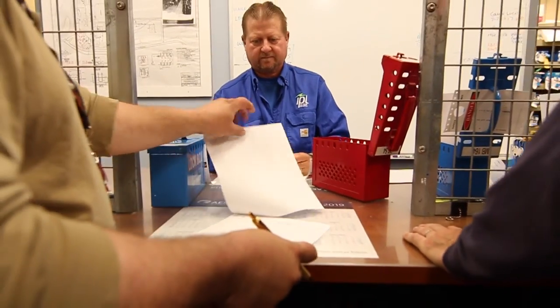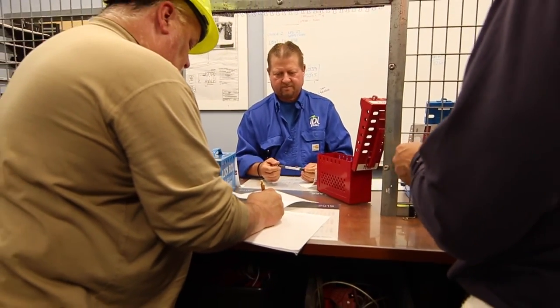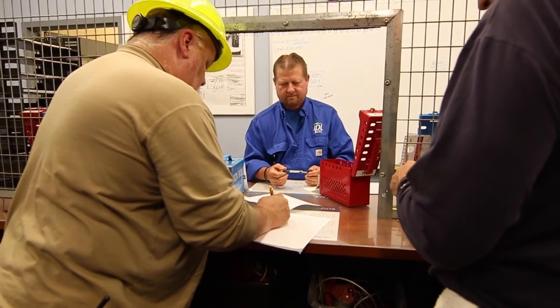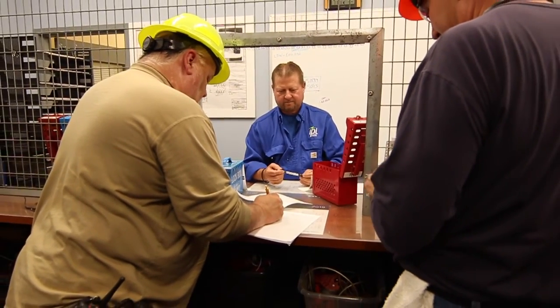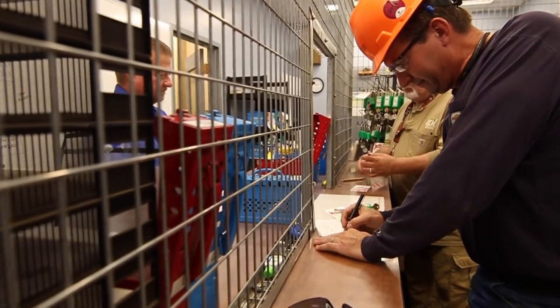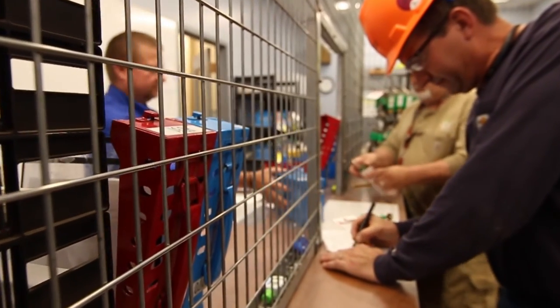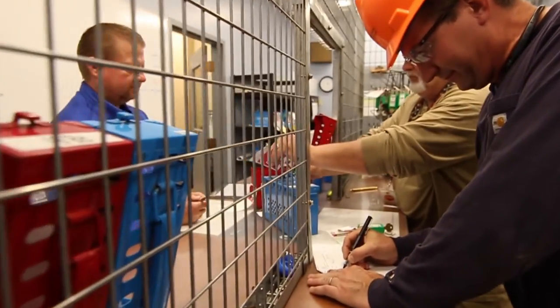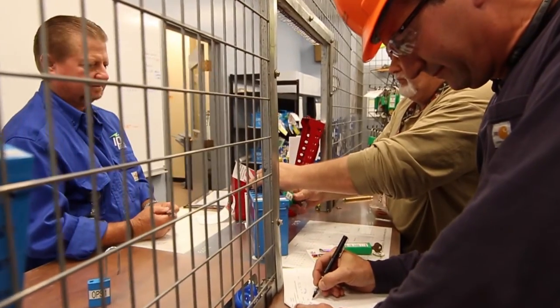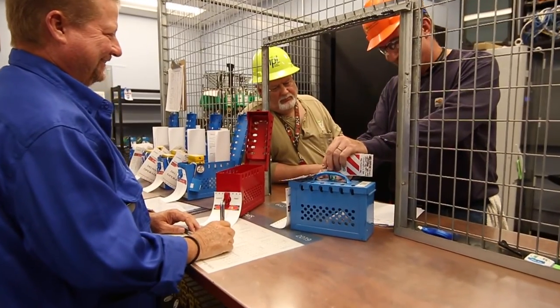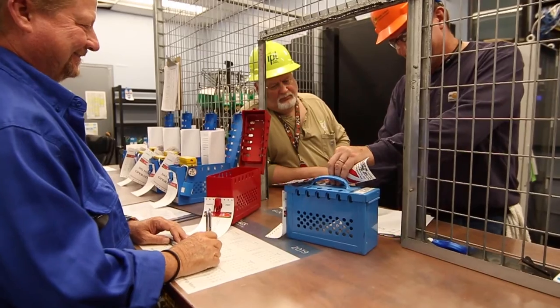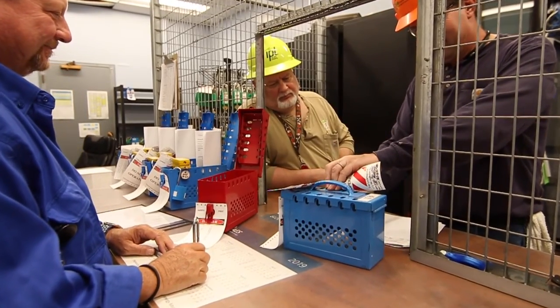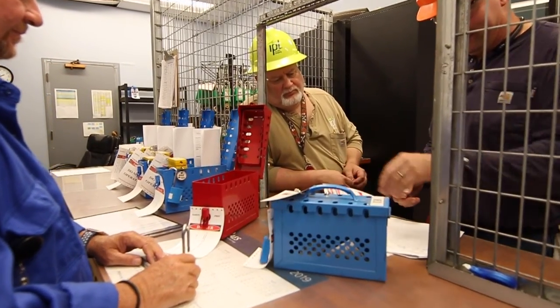You shall receive advanced written approval from the IPL Contractor Administrator to use personal lockout/tagout procedures, and this approval shall be documented on the contractor's project specific form. The IPL Contractor Administrator shall first place their lock on the piece of equipment to be de-energized before allowing the contractor to place their lock. Never place a lock or tag on IPL equipment without proper authorization.